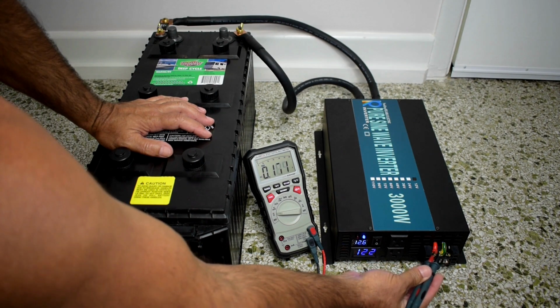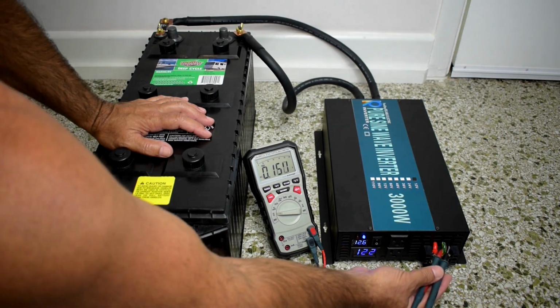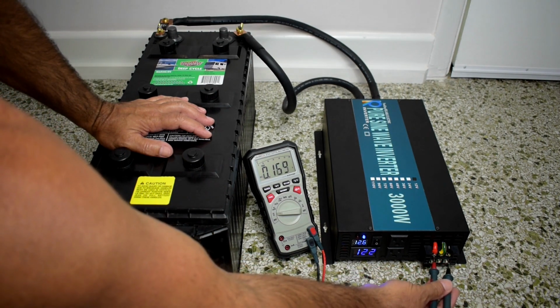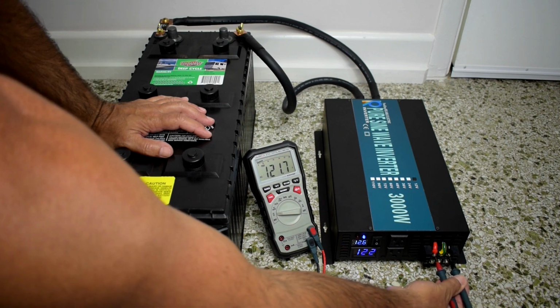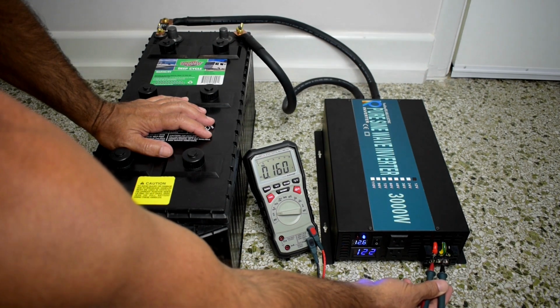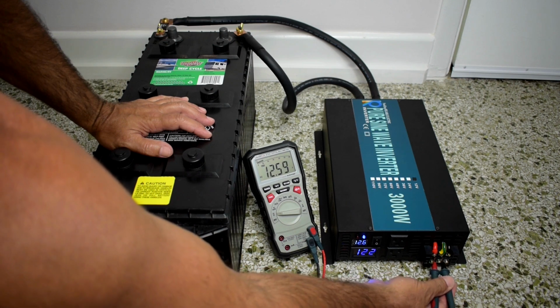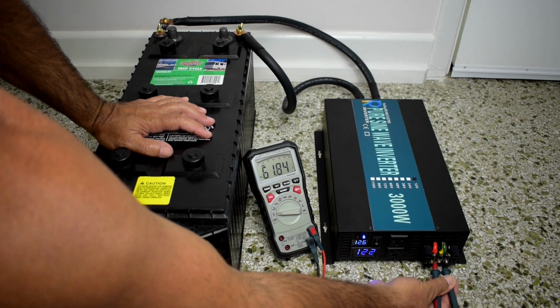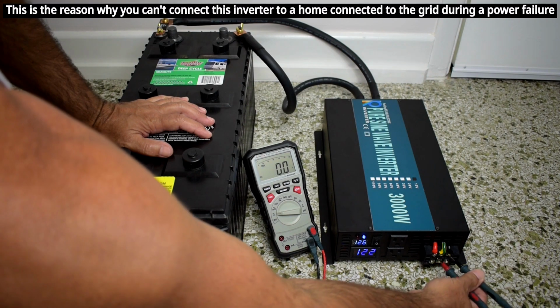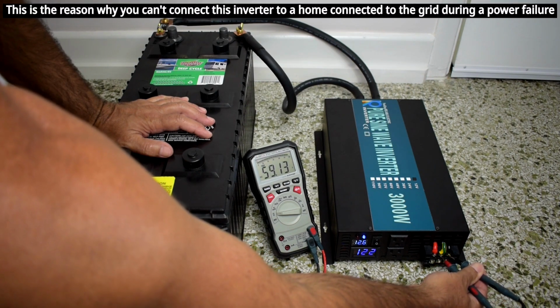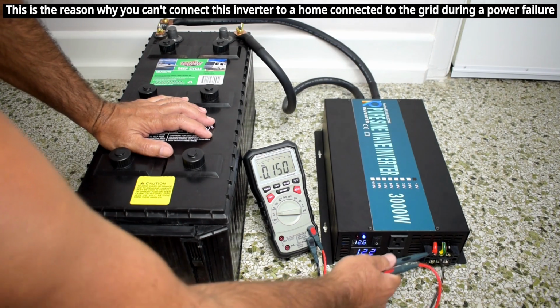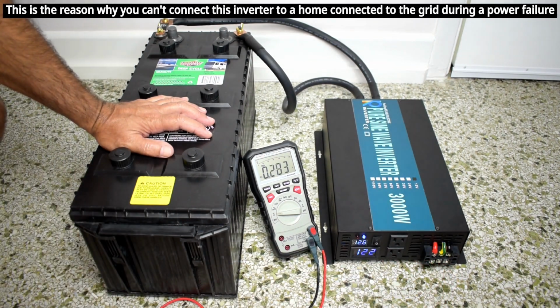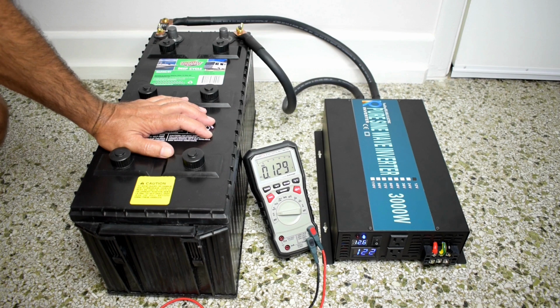Now remember, the red is the line, the black is the neutral, and I made this green because that's ground. Let's go here and there, same as this, and let's measure between line and ground: 61.8. If you go between the neutral and the ground, it's 59. So basically this is center tapped, just like a center tap transformer on a utility pole. The neutral on the transformer is the center tap, so that's why we're getting 60 to here and 60 to there, and 120 across here.